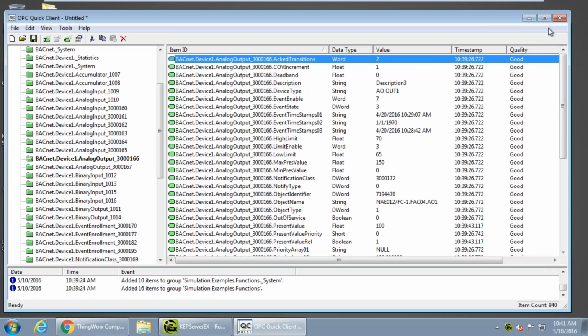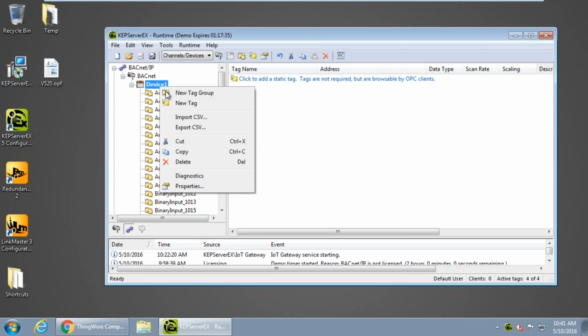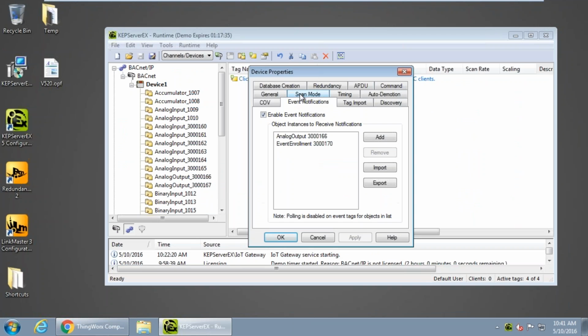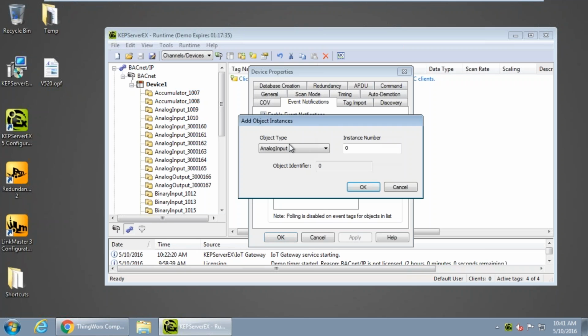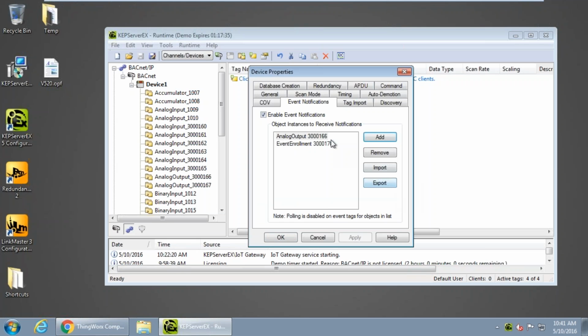And if I get out of the quick client here, that's set up in device properties in this event notifications tab. This tab is new in v520, and if I have that enabled, you can see I'm monitoring my analog output there for alarms, and I can add my object type here. So for any object that supports either intrinsic or algorithmic alarming, I can add the object type and the instance number, and if it's in this list, that means I'm monitoring it for alarms.